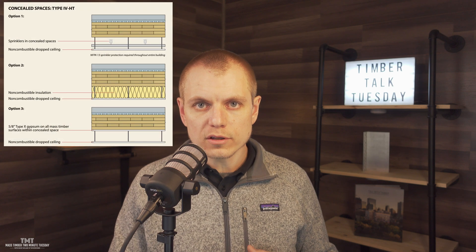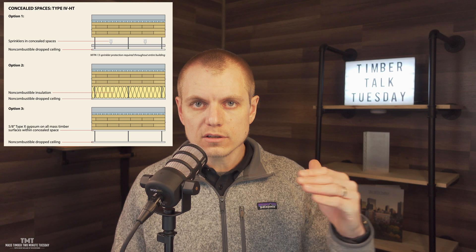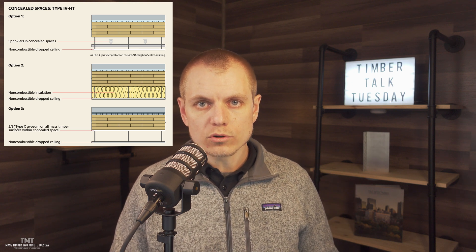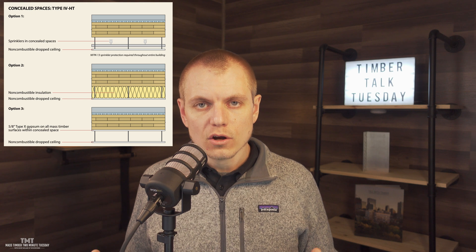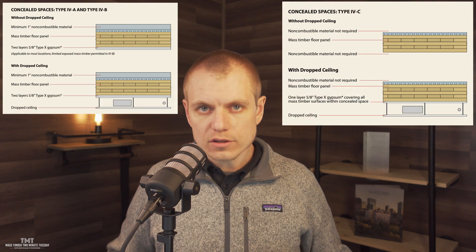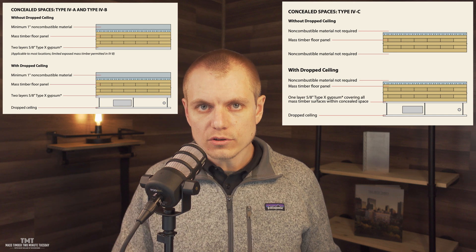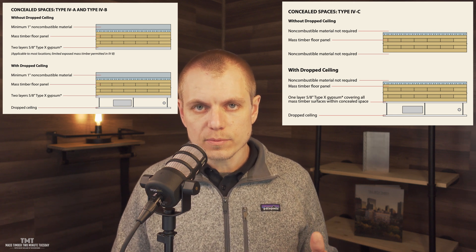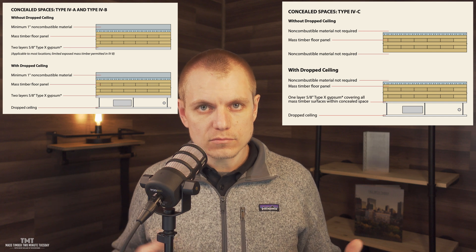In Type 4HT construction we can have concealed spaces, but we must comply with one of three options for protecting the timber within that concealed space: either using non-combustible insulation to fill the cavity between the drop ceiling and the underside of the mass timber floor panel, having sprinkler protection within that concealed space, or encapsulating the underside of the mass timber floor panel. In Types 4C, 4B, and 4A, concealed spaces are also allowed; however, there is a prescriptive requirement across the board that we encapsulate the mass timber within that concealed space with a minimum layer of non-combustible elements.